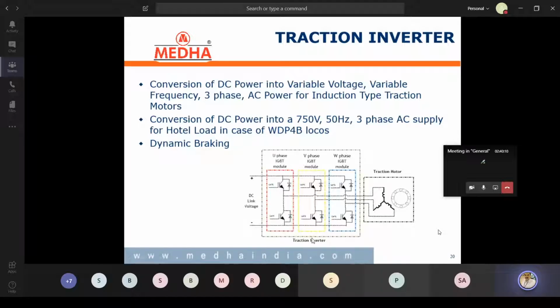Here we can see the traction inverter and motor. Inside the inverter, there are three phase modules, U phase, V phase, W, or R, Y, B, anything. In each phase module, one top IGBT, one bottom IGBT. And this is the IGBT symbol with its anti-parallel diode. Inside the IGBT module, this diode is also there. Commonly for all the three phase modules, we give DC supply, that 600 to 2600 volts DC. And as per the computer commands, these IGBTs will be triggered one by one. At a time, in one phase module, only one IGBT, either top or bottom. If both IGBTs are triggered or fired mistakenly, the entire DC link will get short circuited. So from both the software and hardware side, we have taken care not to close both the IGBTs at a time.